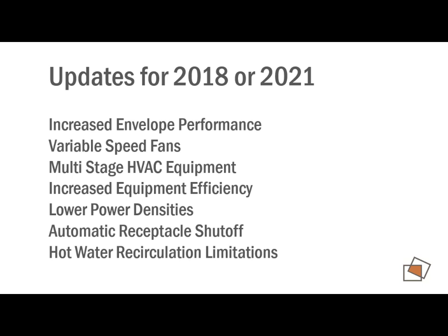Our equipment efficiencies are going to have to be more efficient, or wattage is going to have to go down. The lighting power densities are going to have to go down. One of the big things in HVAC is there are requirements for variable speed fans and multi-stage compressors. So it's just the ability of units to turn down in their operation. When they're not at full load, they can turn off a stage or modulate down. It's going to be great for conditioning, but it's more costly equipment.